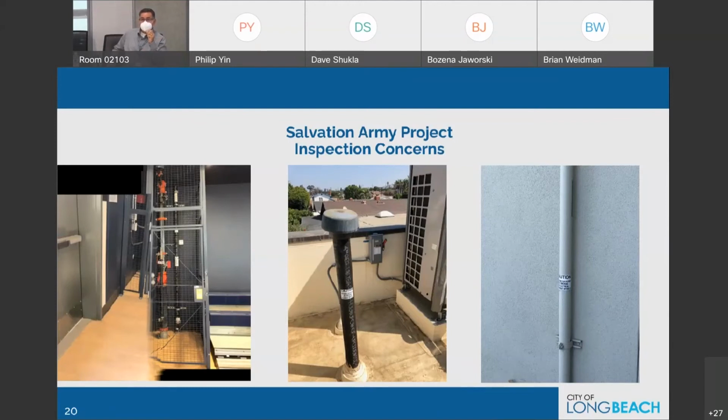And if you see the pipe or vent is terminated with an approved rain guard that meets code for this vent riser, which is identified also with the type of system it belongs to. It says caution, and again, caution methane within this pipe normally, and no sparks or electrical equipment within 10 feet. So as we can see, there's a disconnect in the back. There's a mechanical unit right next to it on the right side.